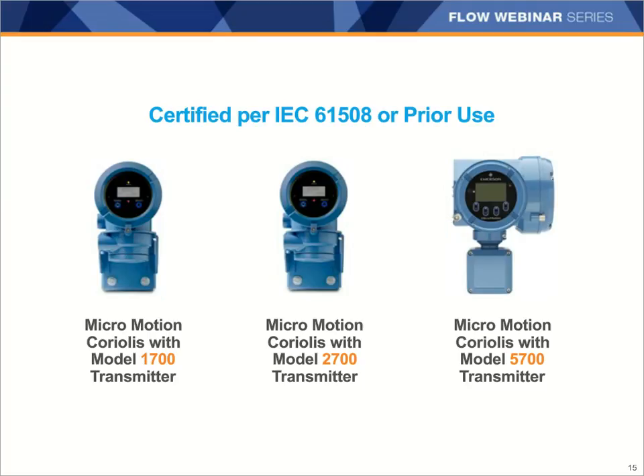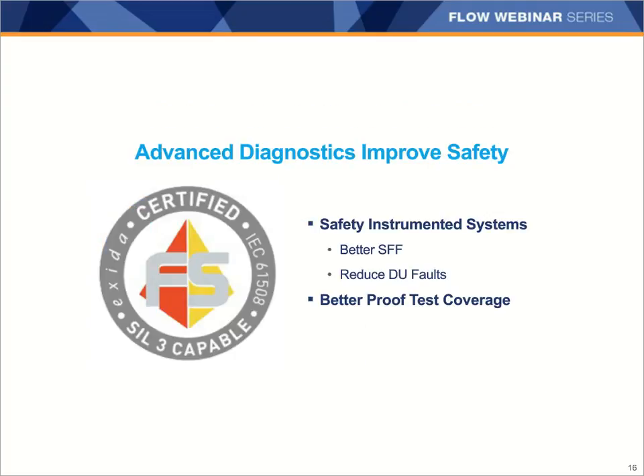In addition to the improved process information and reduced potential leak points, I wanted to briefly talk about how diagnostics have improved over time and have resulted in additional safety improvements. As you're probably quite aware, in any safety instrumented system, safety scores and SILs, or safety integrity levels, are highly impacted by diagnostic capabilities. As instruments are developed with more and more diagnostics, more of the dangerous faults of the device can be detected. This means that dangerous undetected, or DU, failures will be lower and your overall safe failure fraction, or SFF, will improve. This results in improving the overall score of the device and can often mean that a device will be rated for a higher safety integrity level.